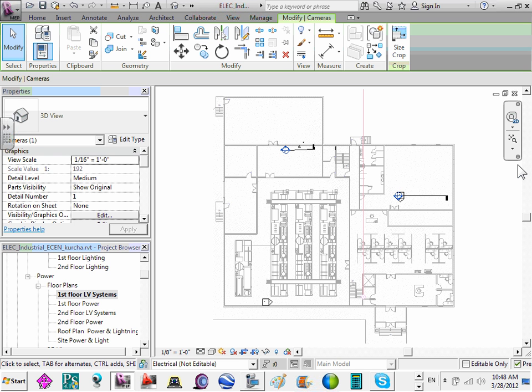And we can go. Your tamper switches that you're going to be monitoring, those are the big turn wheels to turn the system on and off, because you want to make sure that the system is always on. If someone comes up and starts messing around and turning off your sprinkler system, and then all of a sudden something happens, it's a big liability. Typically you'll see them chain locked. The only people that are allowed to turn off the sprinkler systems are the fire department, and the sprinkler contractor when they're doing service on it.